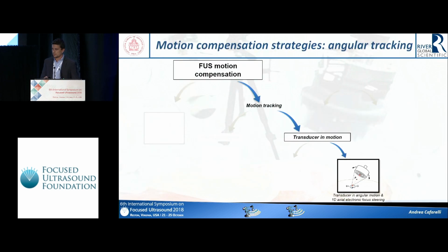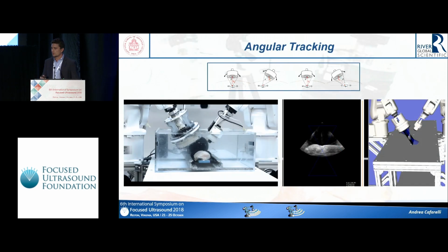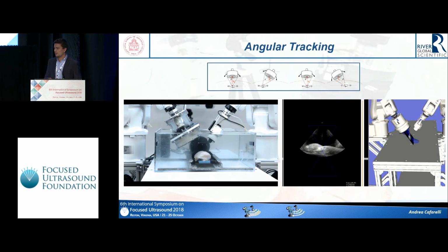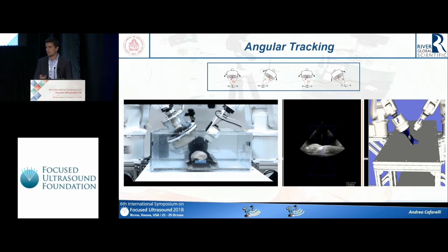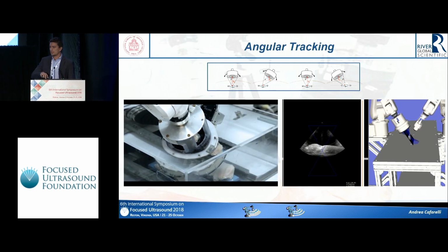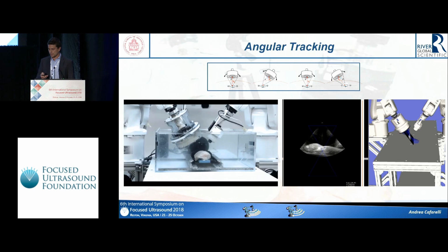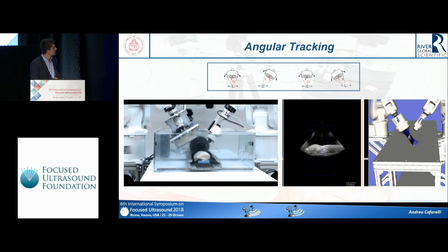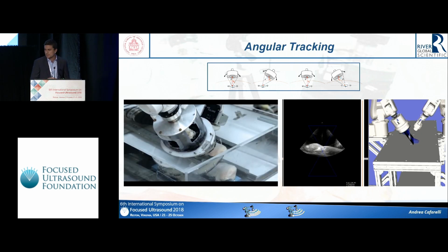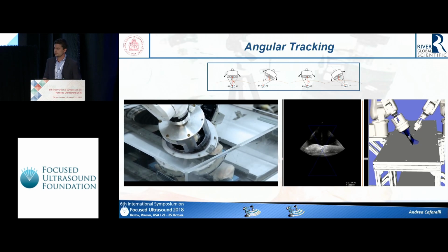The different approach that we are trying to demonstrate is the angular motion of the transducer. In this case, we can fix a pivot point, so there is a minimization of the modification of the acoustic window. The transducer moves angularly, and as you can see from the image, only the focal point is fixed on the screen.